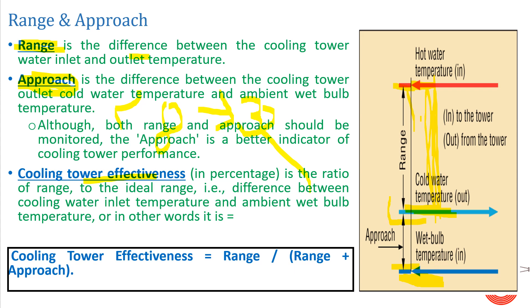Cooling tower effectiveness is the ratio of range to the ideal range — that is, the difference of cooling water inlet temperature and ambient wet bulb temperature. Simplified, it equals range divided by (range plus approach). If you want to know how effectively your cooling tower is working, you calculate it as range upon range plus approach. This is an important terminology that designers use to calculate the effectiveness of a cooling tower.